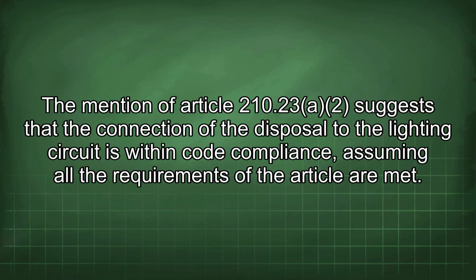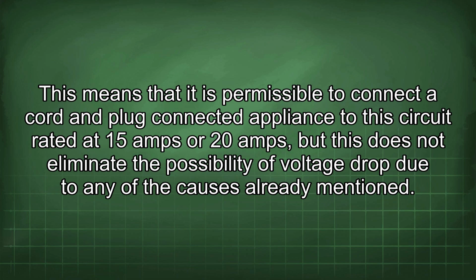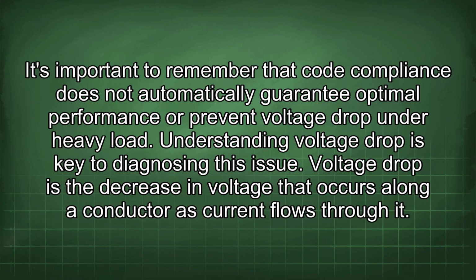The mention of Article 210.23(A)(2) suggests that the connection of the disposal to the lighting circuit is within code compliance, assuming all the requirements of the article are met. This means that it is permissible to connect a cord and plug connected appliance to the circuit rated at 15 amps or 20 amps, but this does not eliminate the possibility of voltage drop due to any of the causes already mentioned. It's important to remember that code compliance does not automatically guarantee optimal performance or prevent voltage drop under heavy load. Understanding voltage drop is key to diagnosing this issue.